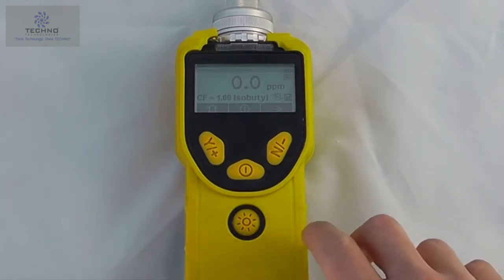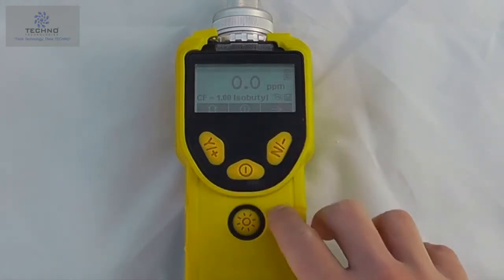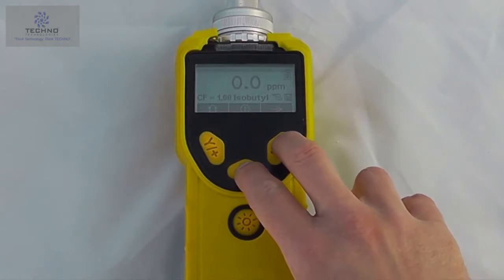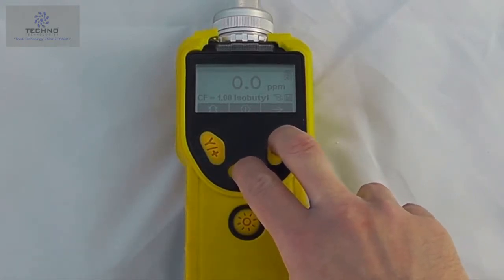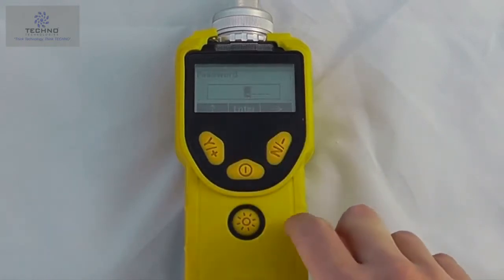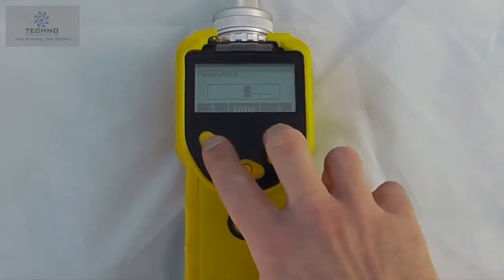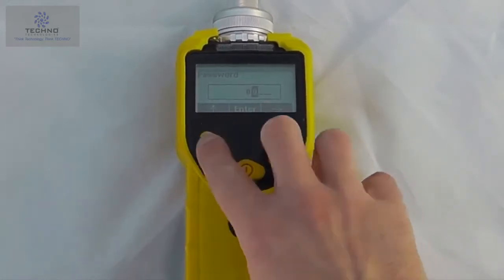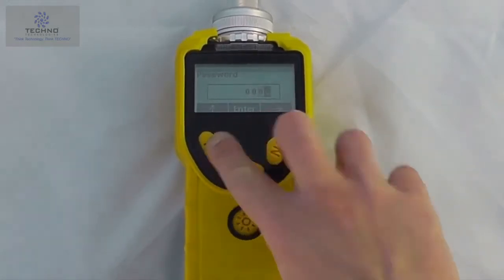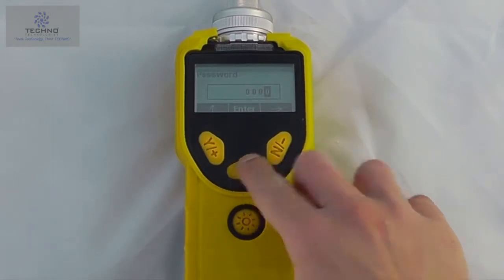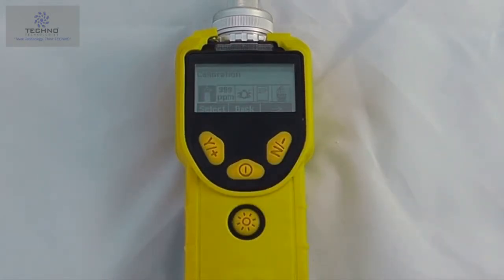So to enter the menus, you press the mode and no button simultaneously. Holding those two buttons together, you will then be asked for a password. The password as standard is set to 0, 0, 0, 0. Enter to go in. Now our first option is a calibration.